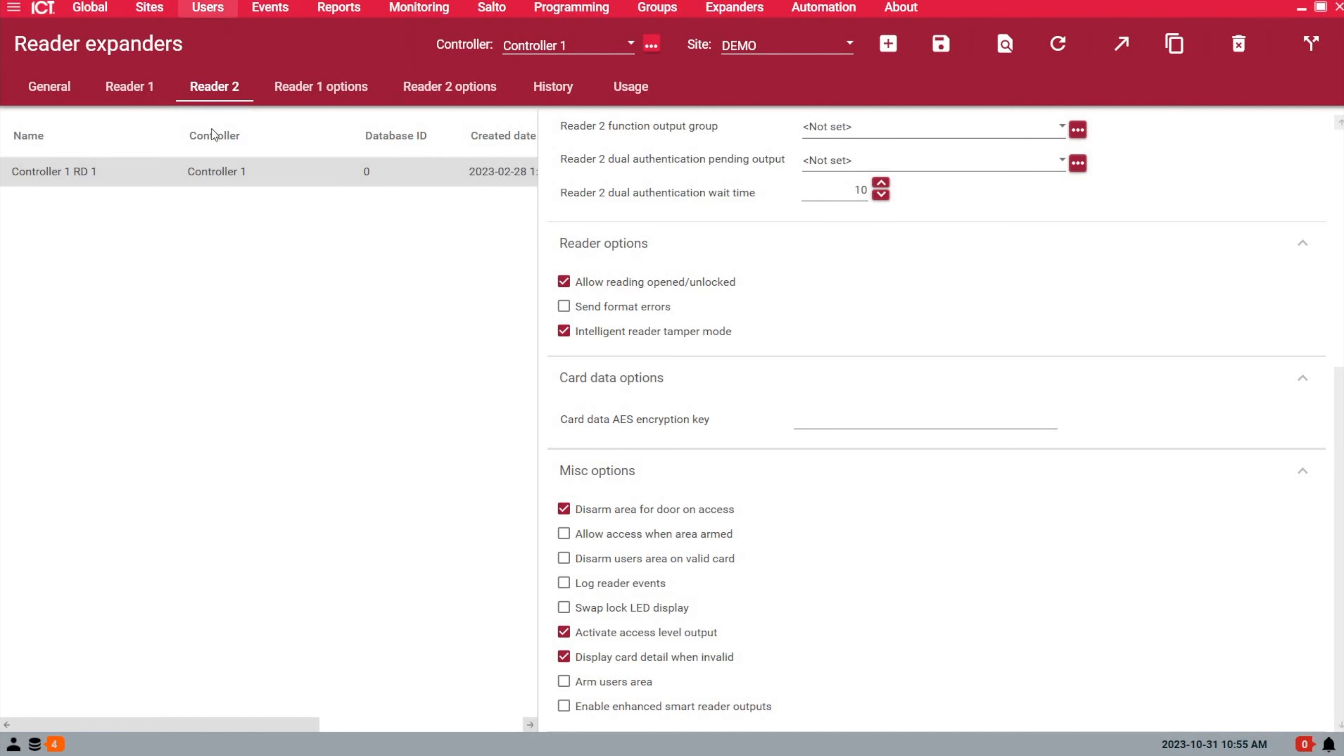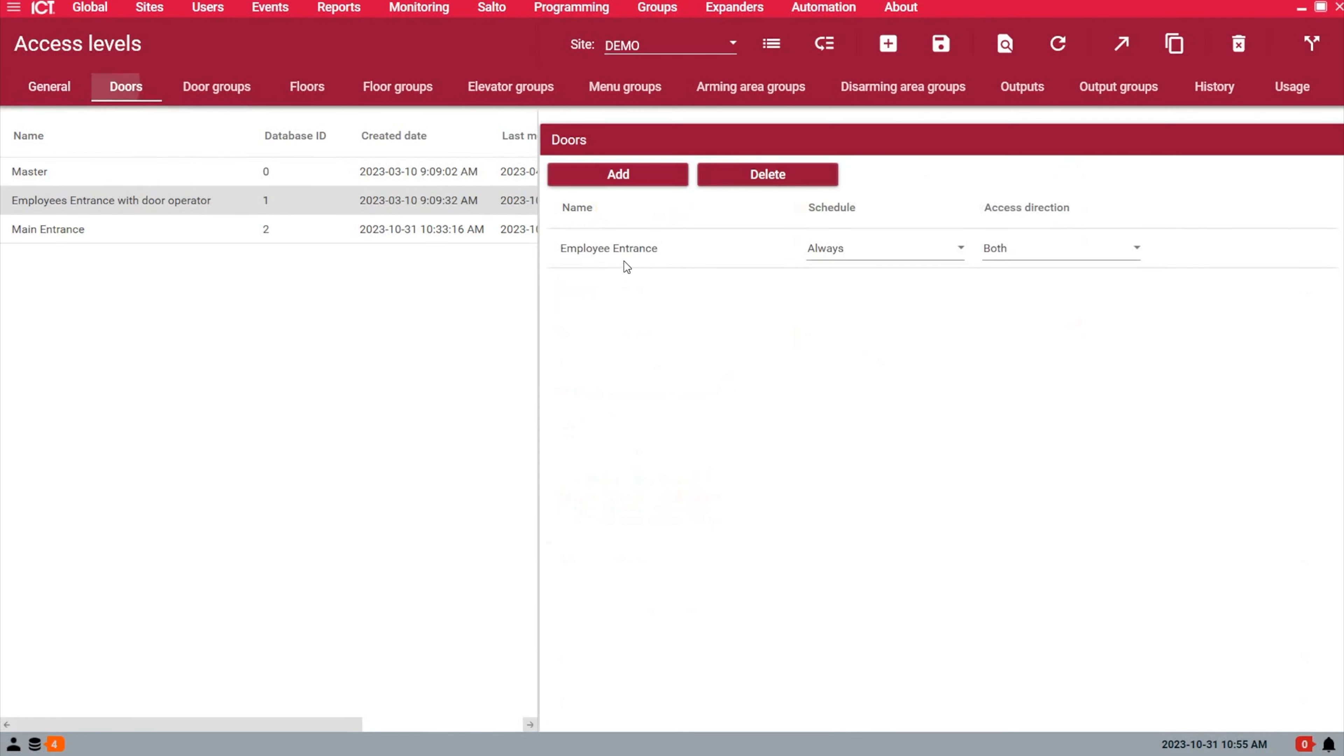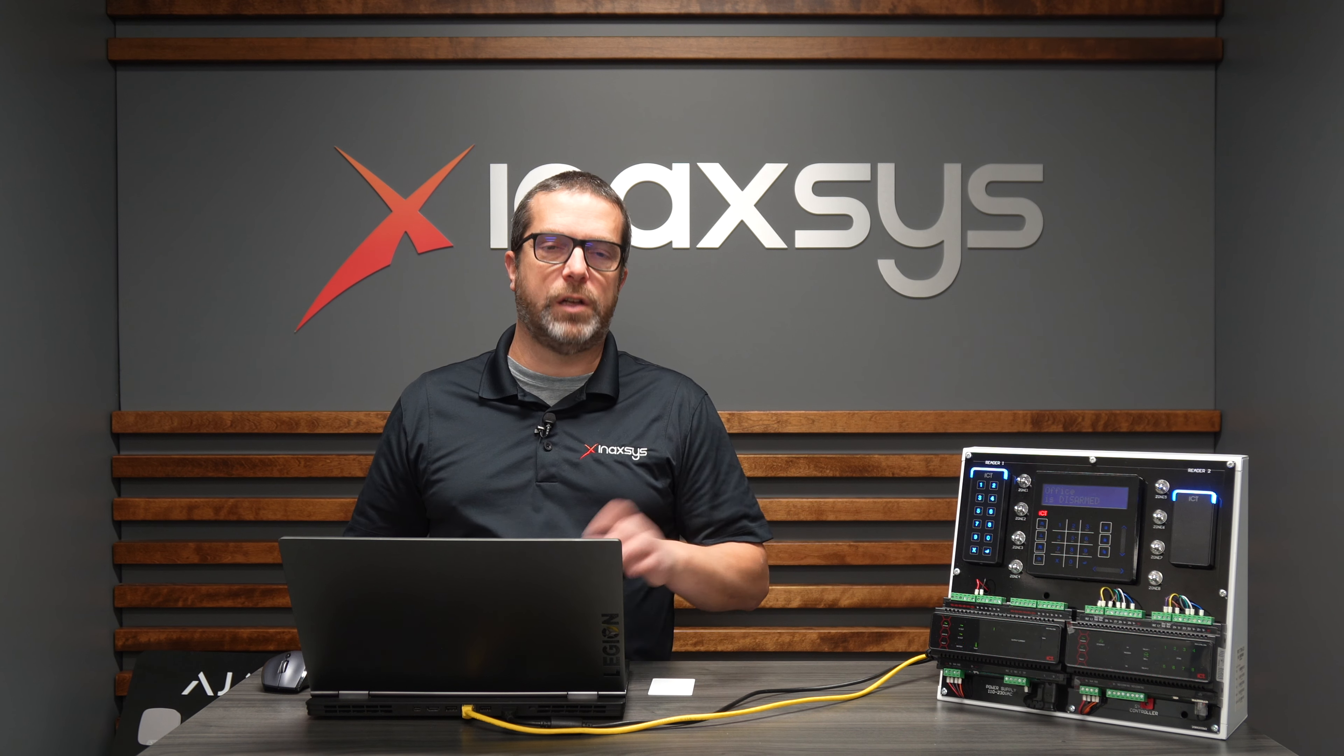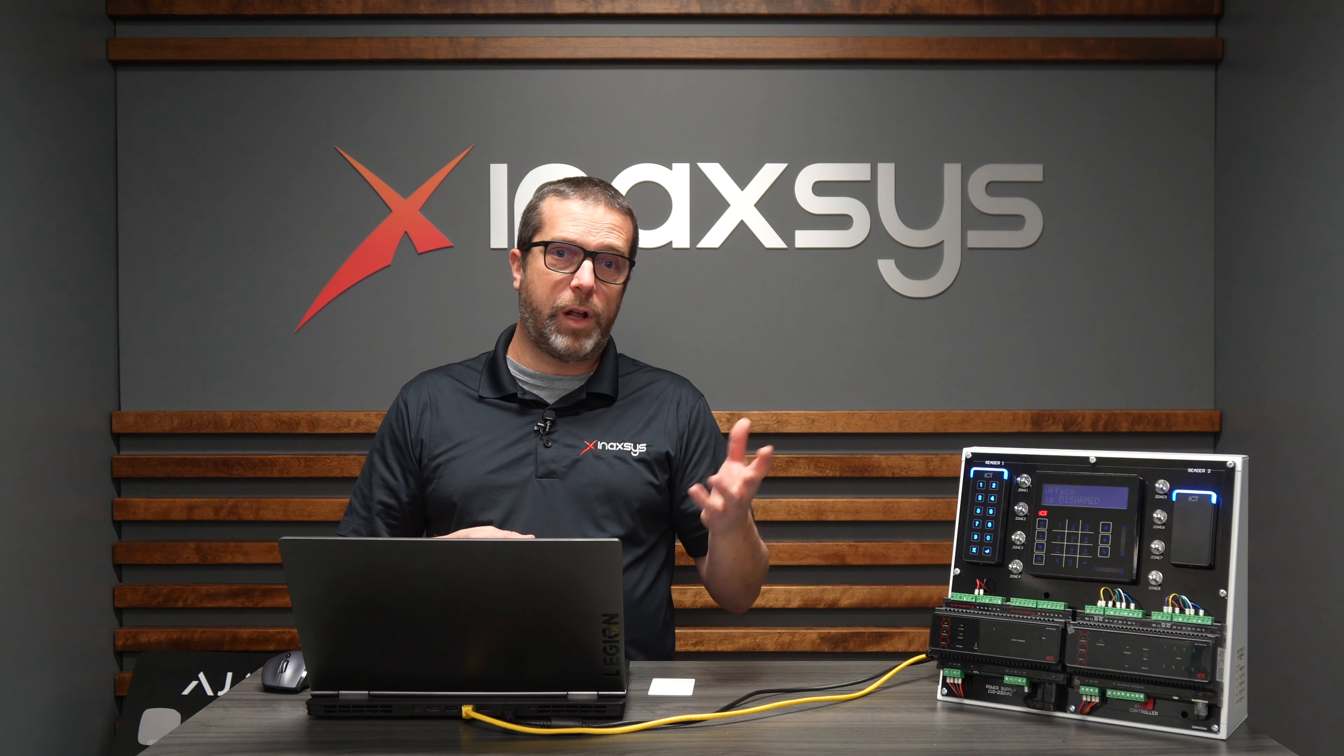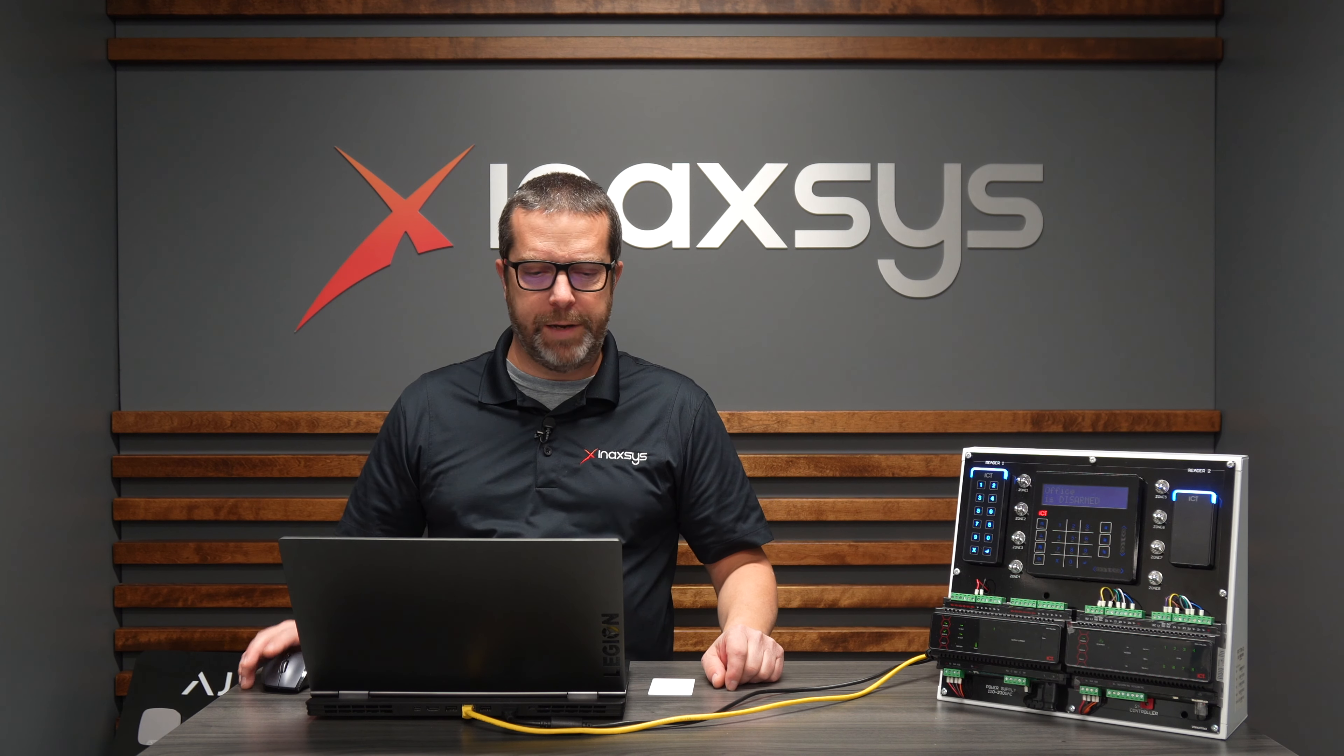The second step is to go to Users and Access Levels. I created an access level just with the employee entrance door. If you put multiple doors in this access level, the output would trigger on different doors, which isn't what you want. If you want the employee entrance door to trigger one output and another door to trigger a different output, you'll need to create separate access levels.